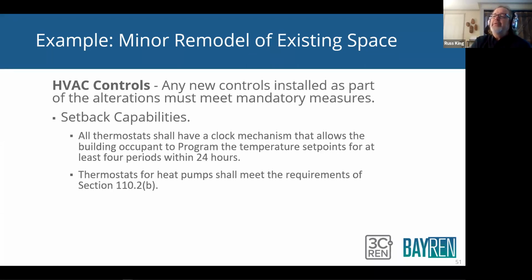Controls: any new controls installed as part of the alterations must meet mandatory measures. One of the big ones is the setback thermostats, right? All thermostats shall have a clock mechanism that allows it to program for 4 periods in 24 hours. Heat pumps have special requirements for thermostats, and there's a code section for that.